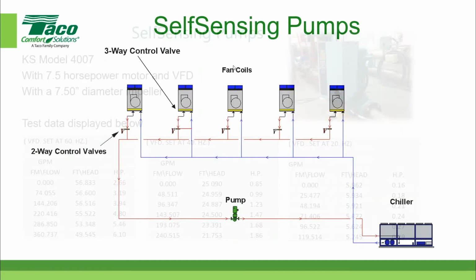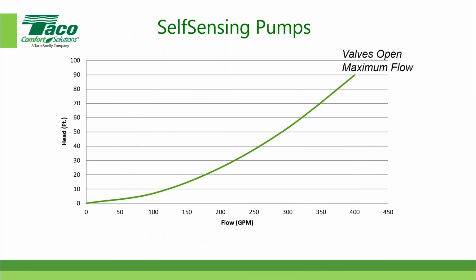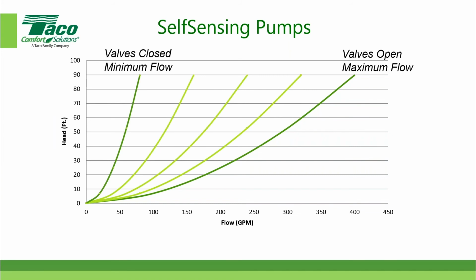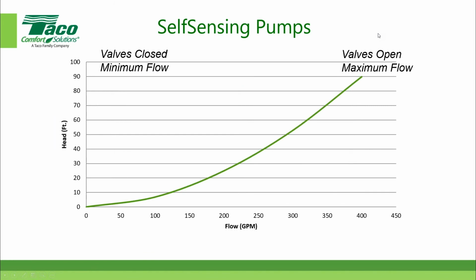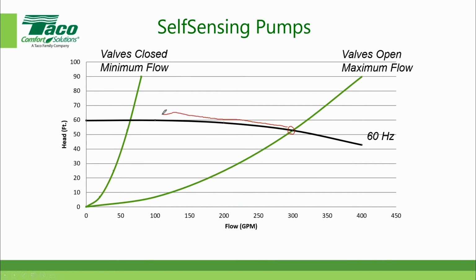Okay, so now let's take a look at our system curve one more time. This system curve is the same one I showed you earlier with all the valves 100% open. As the valves close, the system curve bends upwards to the left, so we get multiple system curves depending on valve position, until we get all the valves closed with the exception of the three-way valve where we maintain minimum flow.